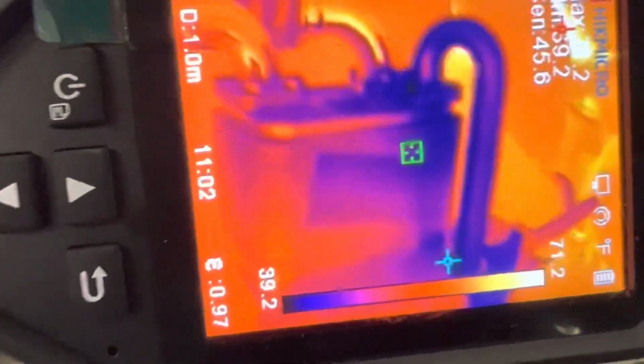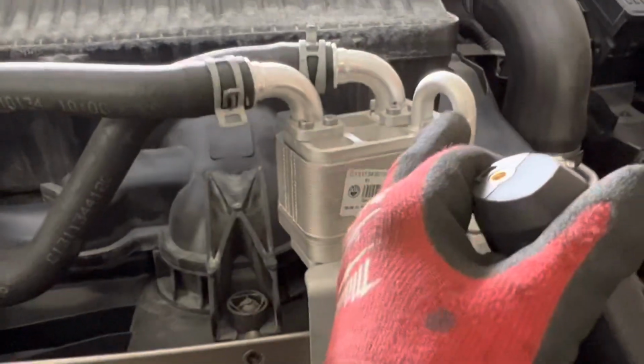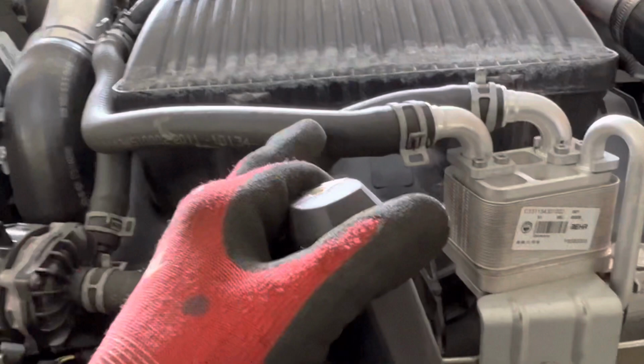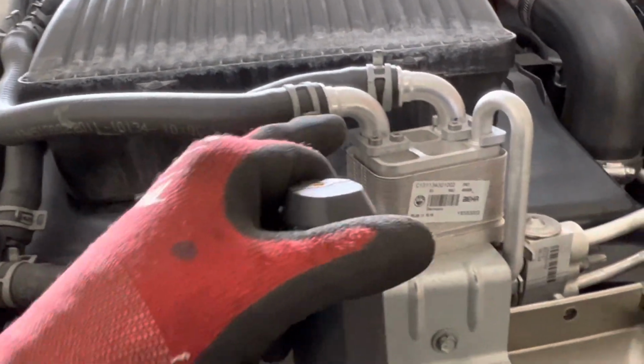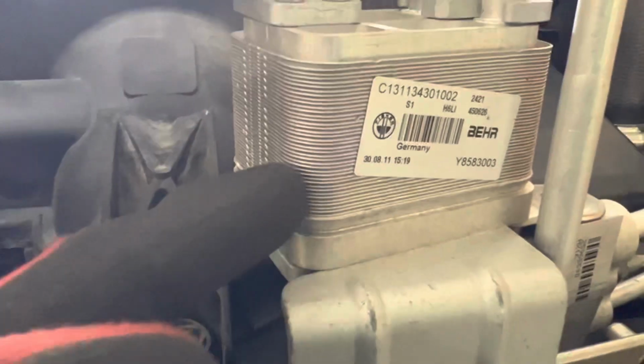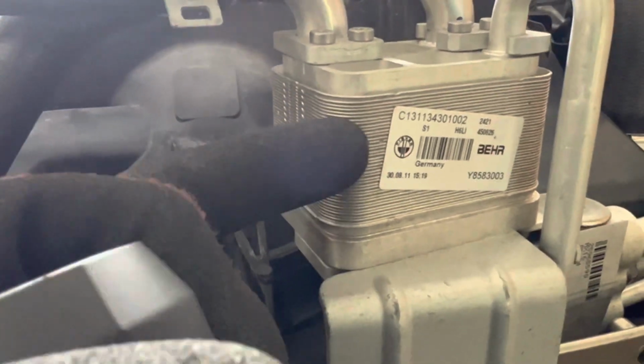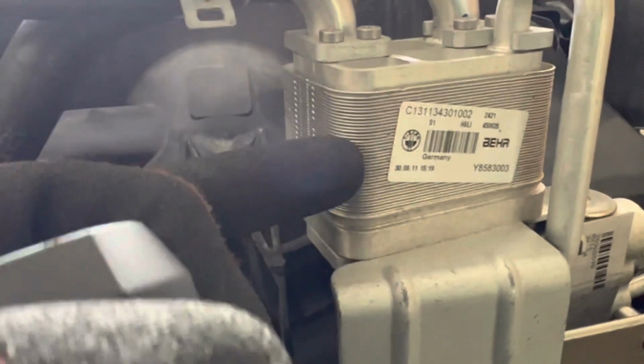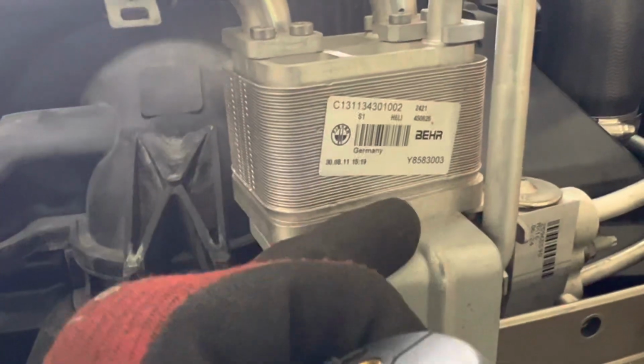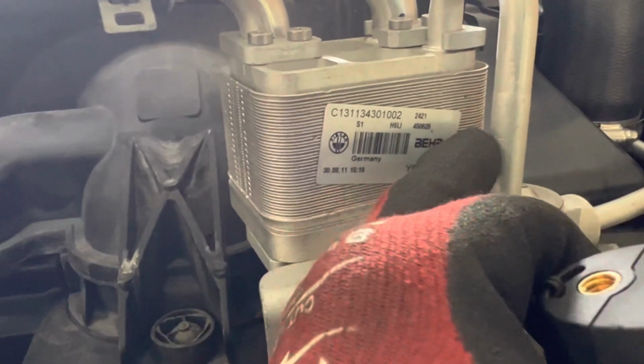It's hard to do this because it's made out of aluminum and very reflective, but you can see the cold refrigerant entering right here, and the hot coolant entering right here. It goes through the plate heat exchanger, and every one of these little stripes is a separation. In between, half of it is liquid coolant going in one direction, and half of it is liquid or vapor refrigerant expanding and cooling in the other direction.